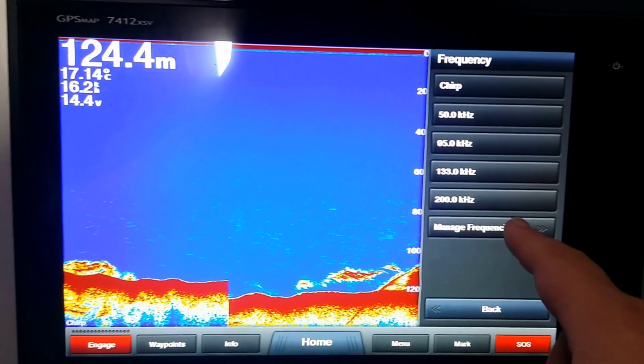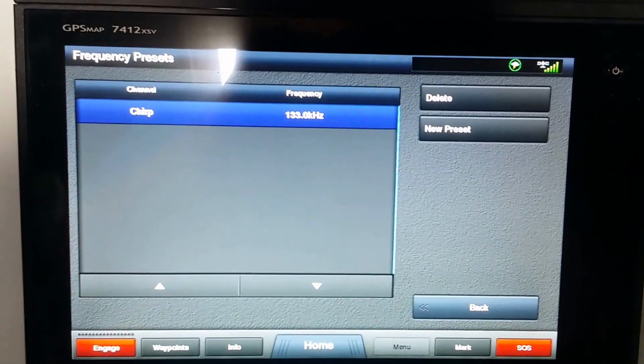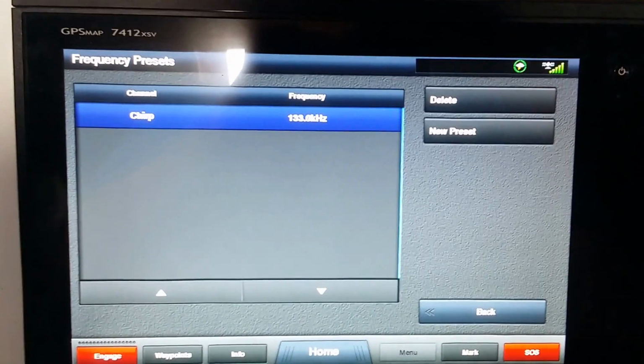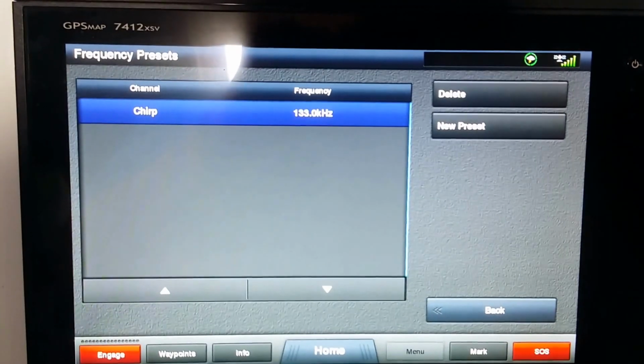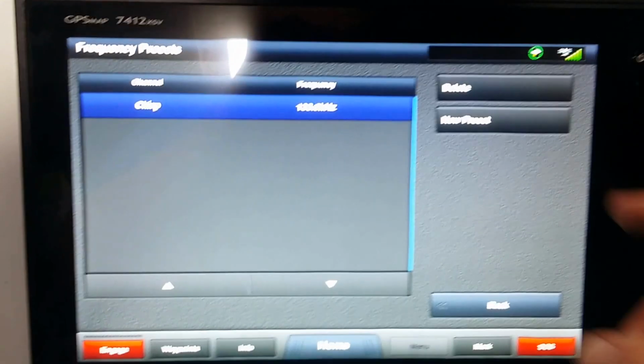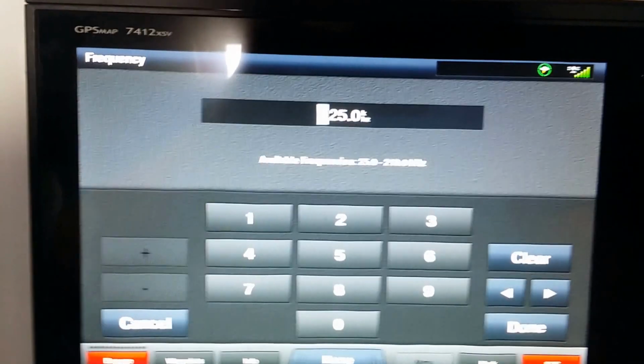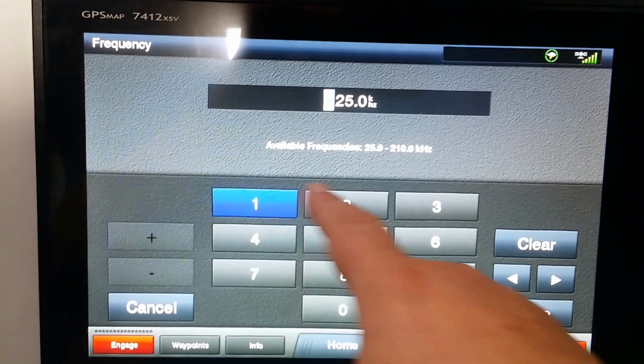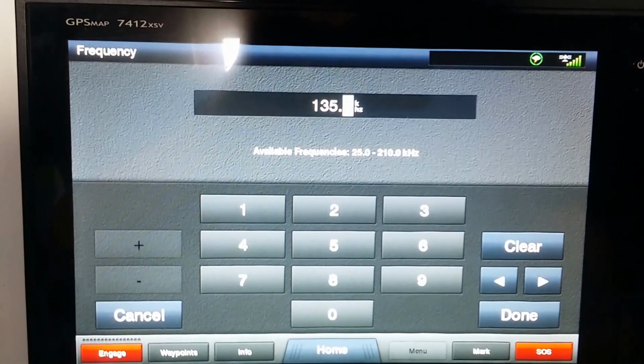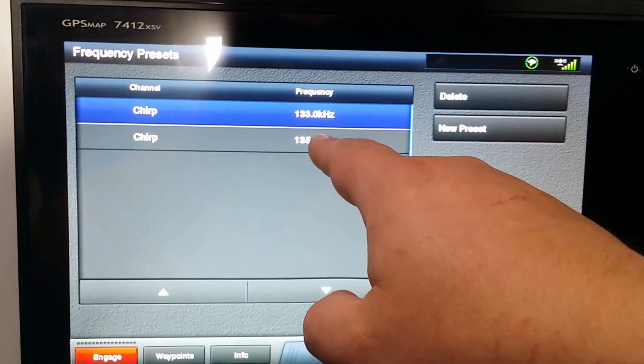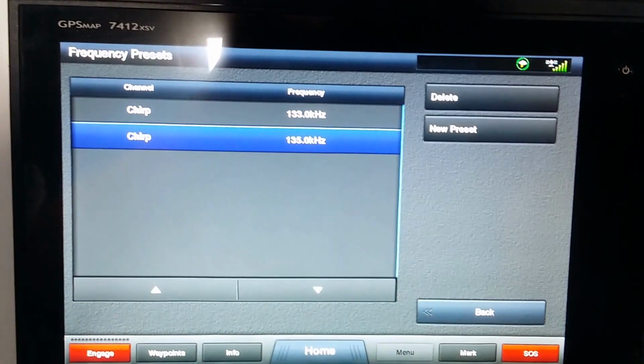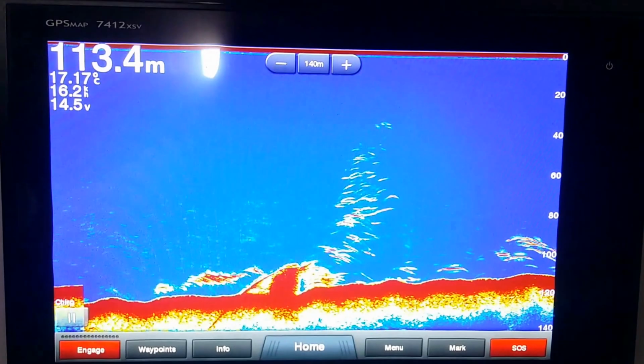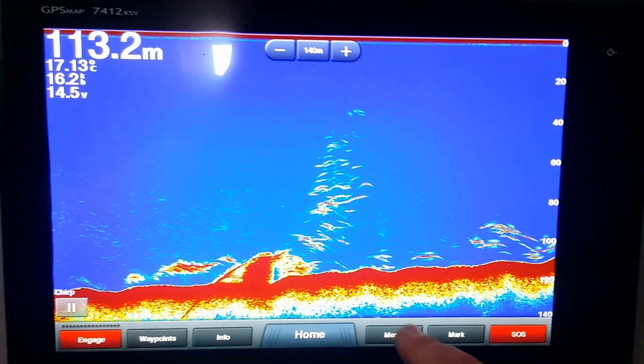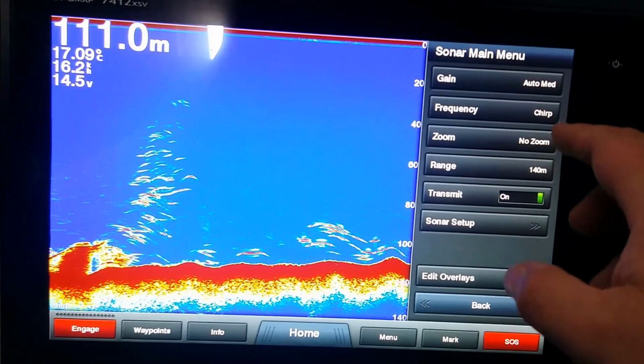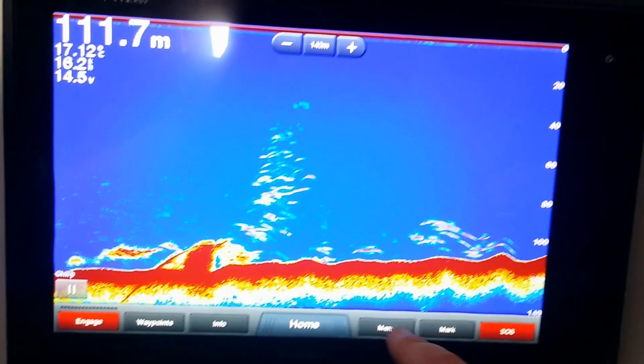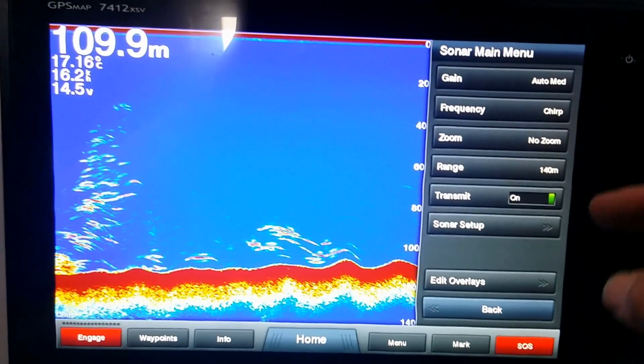With chirp transducers, we can dial in a particular frequency. Let's say, for example, you have a TM150, which is a medium frequency chirp transducer. We can go into new preset, and we can dial in, say, 135 kHz. Press done. It's in our bank of memory. We select it, press back, and now we're running at 135 kHz. If I press menu, I'll go back to chirp, we also have zoom.